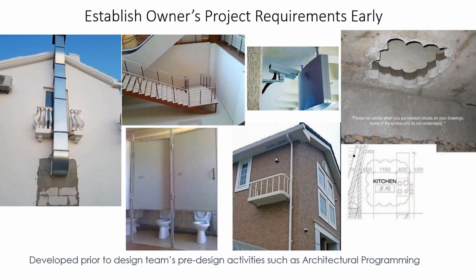One good example is networking requirements, not having any IT requirements included in the initial information or initial meetings. It's always left as a secondary thought. But having those IT requirements early on, making sure they're set, makes it much easier to size mechanical equipment, both for the IT rooms and the size of the IT rooms themselves, so the architecture can utilize as much of the space as possible. These coordination issues end up slowing down projects, resulting in wasted space or wasted money, all due to not having those clear requirements early on in the project.